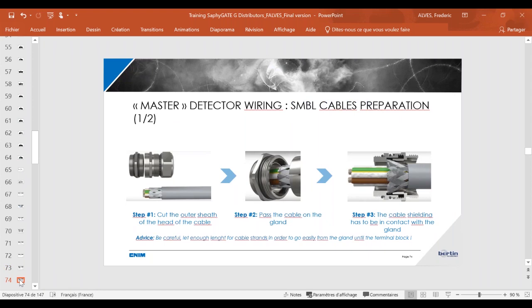Concerning the SMBL cables, here you also have the steps to prepare it as well as possible, to prepare the head, let me say, the head of the cable. So a first step, since you have passed the SMBL cable on the gland, be sure that the shielding part is in contact with the gland. Okay, this is really important. And another point that is really important is the length of the cables. An advice: be careful, leave enough length for the cable strands in order to connect it easily on the terminal blocks. Okay, be sure that you have enough length on this cable.